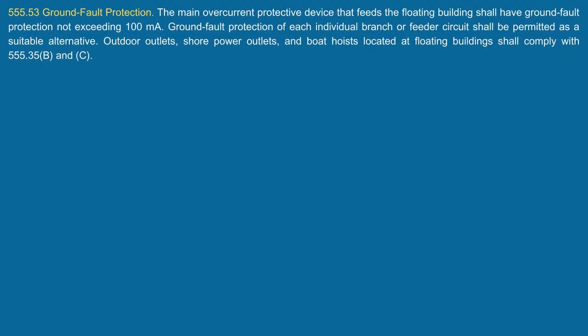And then it talks about ground fault protection. It says the main overcurrent device that feeds the floating building shall have ground fault protection not exceeding 100 milliamps. Ground fault protection for each individual branch or feeder circuit shall be permitted as a suitable alternative. And then it says outdoor outlets, shore power outlets, and boat hoists located at floating buildings shall, looky here, comply with what? Where we started, 555.35(B) through (C), which says they're what? Receptacles. Yep.